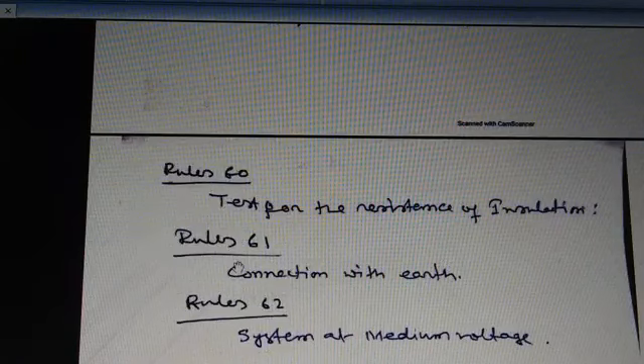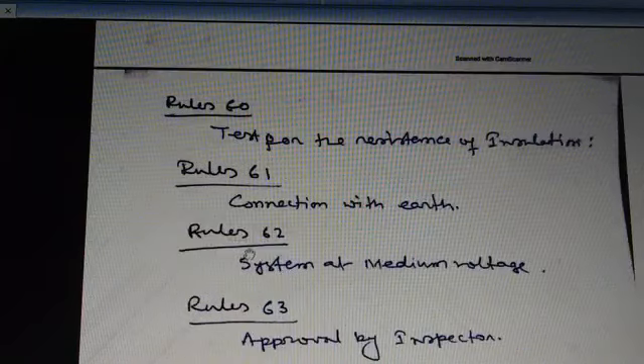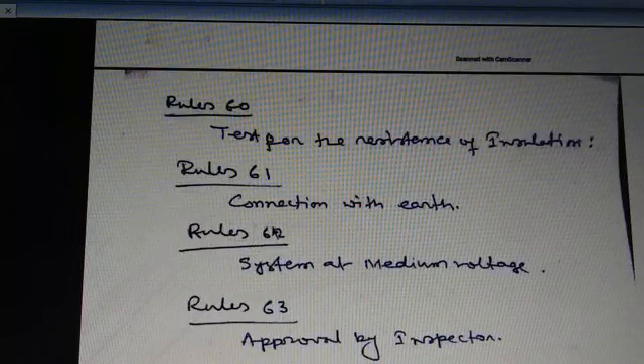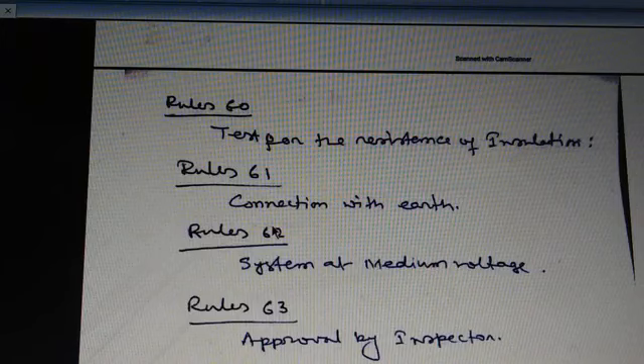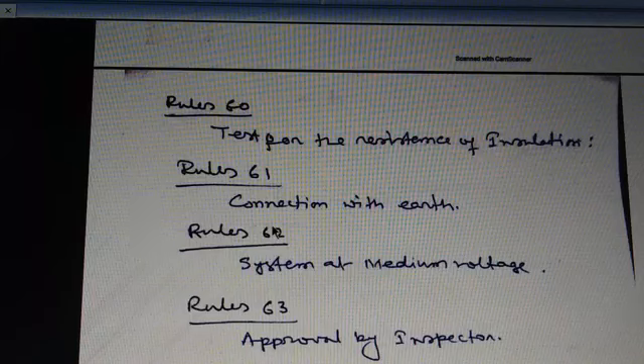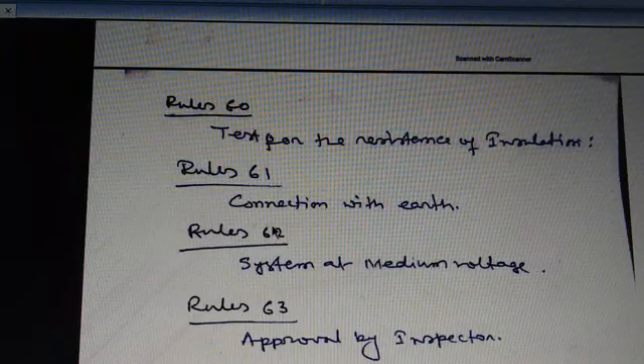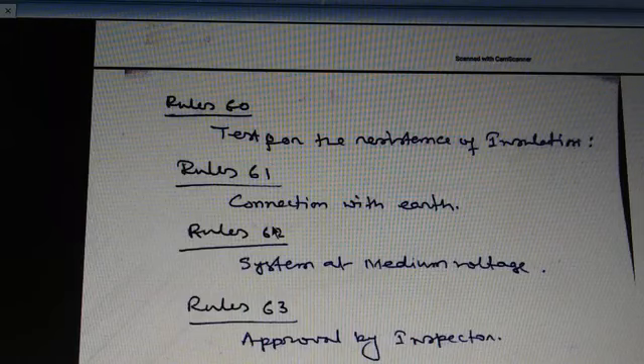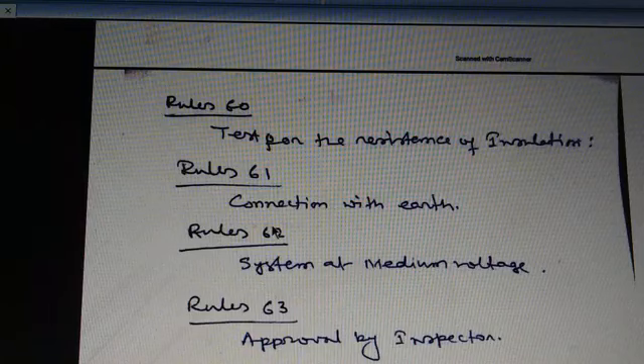Now rule number 61, connections with earth. The following provisions shall apply to the connections with earth of the system at low voltage where the voltage normally does not exceed 250 volts, and of the system at medium voltage. First point, the neutral conductor of a 3-phase 4-wire system shall be earthed by not less than 2 separate and distinct connections with earth, both at the generating station and in the substation.